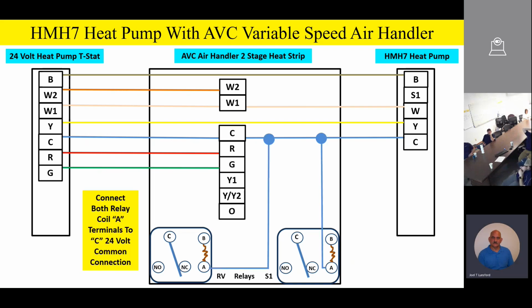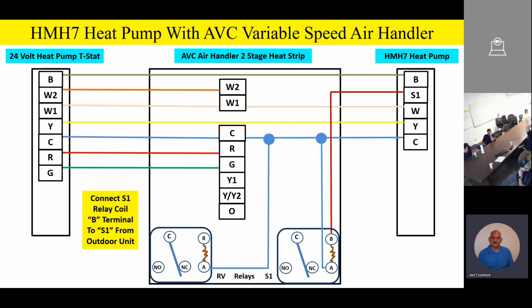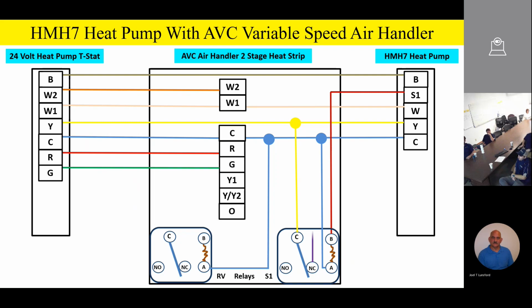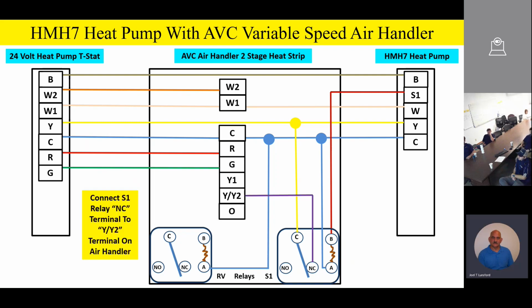As we take a look at those relays, one side of both relay coils is going to go to 24-volt common. On the other side of the relay, the B terminal, or the other side of the S1 relay, goes up to the S1 terminal. This is going to be our airflow reduction relay like we had before on the other products. We're going to have the Y terminal feeding the common switching point for the switching contacts on the relay, 24 volts to common on the contact. The normally closed contact on the S1 relay will go to Y/Y2. The normally open contact on the S1 relay will go to Y1. Again, this is our airflow reduction.